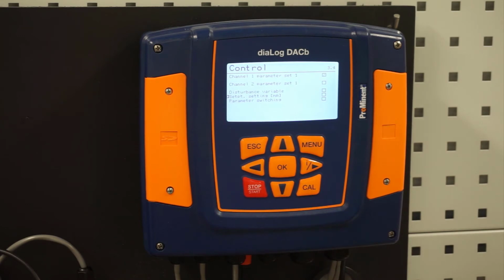Set point setting is not typically used, but what you could do with it is bring in a switch or a signal from the control room into one of those digital inputs. Remember, we have 7 of those. And anytime we switch that switch from one position to another, it would change the set point.